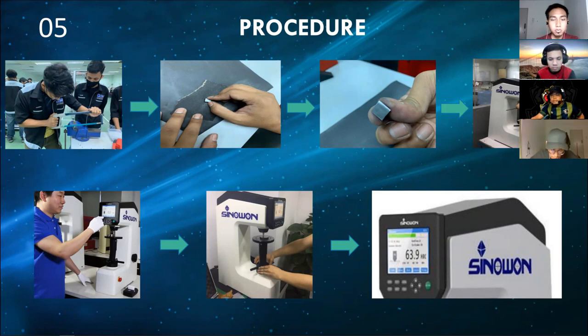Place the specimen on the anvil properly and slowly turn the elevation handle clockwise so that the specimen contacts the indenter, then stop when the indenter bar is full; the test is initiated automatically with a click sound.